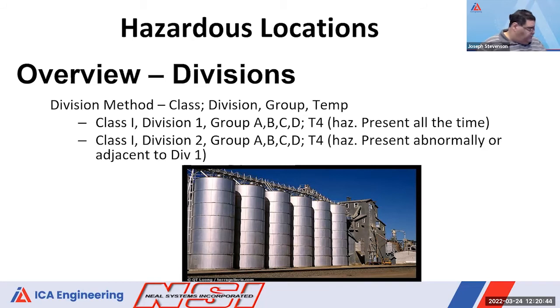And that's especially important in a large facility where you may have electrical lines or pipes or whatever that are actually moving from one classified area to another. And so it's very easy if you aren't considering those boundaries that you could end up introducing a hazard that you didn't expect. Plus the fact that just because something is not normally expected to be in an area doesn't mean that it won't be there.